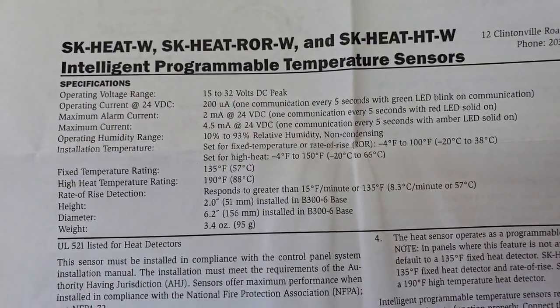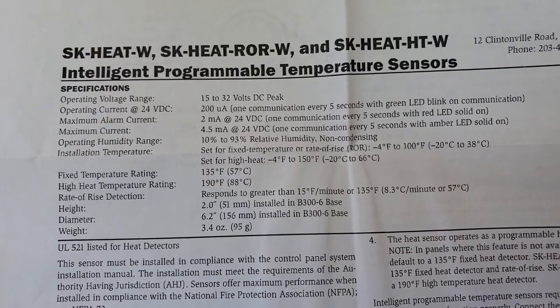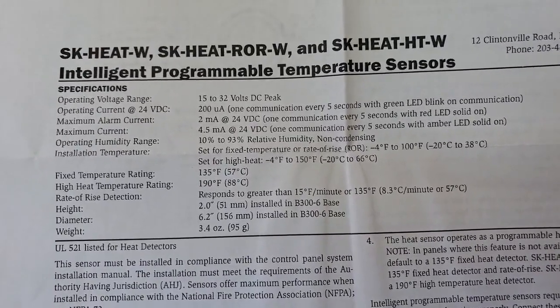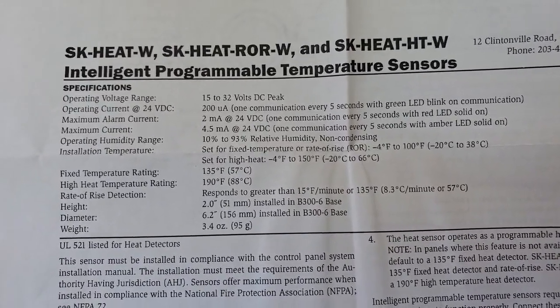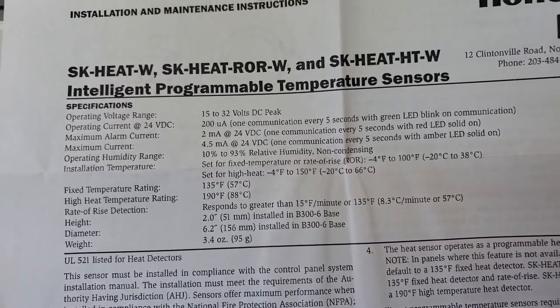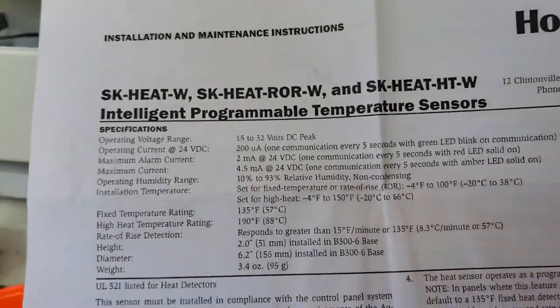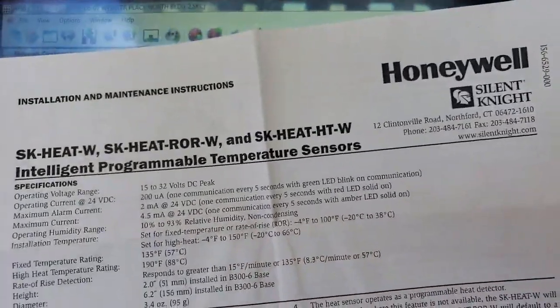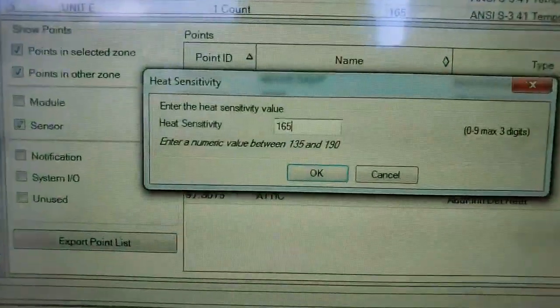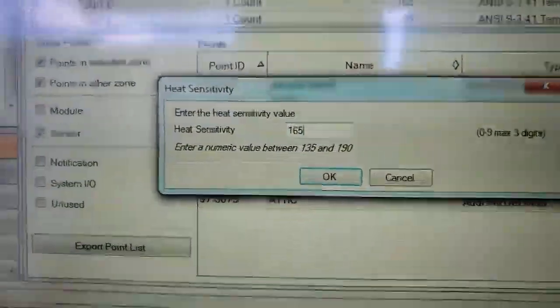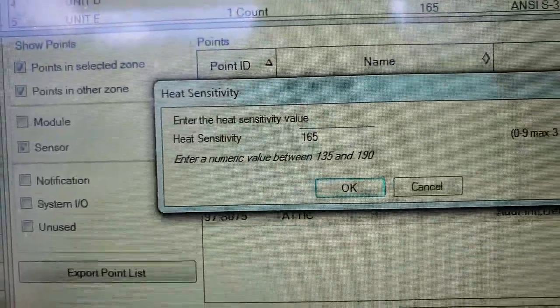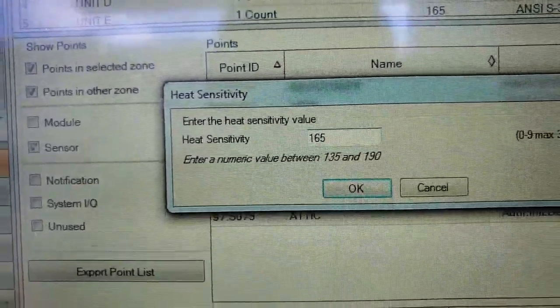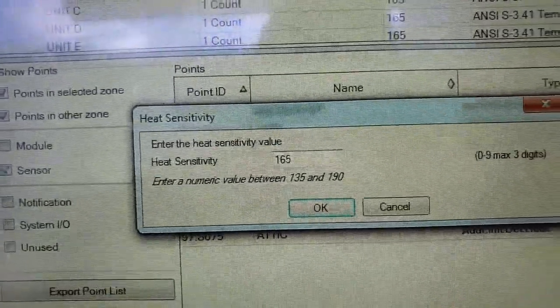And here's the question. What does that apply to? I think when we installed this, we thought that somehow that applied to an SK heat W because we set it to 165 degrees Fahrenheit, which should not have tripped. I mean, experience is telling us now these attics get to 140 on a hot day.